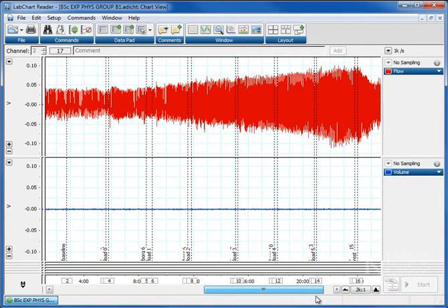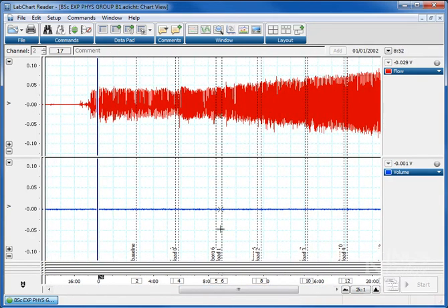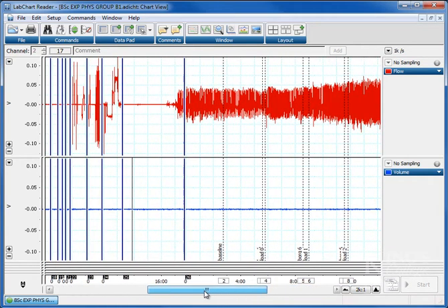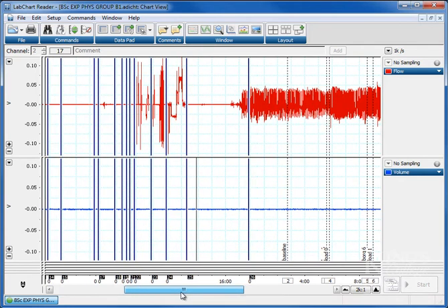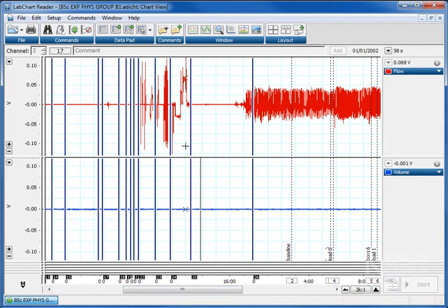Okay, so the data's certainly there, the integration of the flow into volume seems to have disappeared because the module isn't installed on the LabChart Reader software. So all I can say at this point is thank goodness for calibrations. We talked about how important calibrations were, and this is a prime example of how important recording your calibration is, not only doing it but actually keeping a copy within each data file.